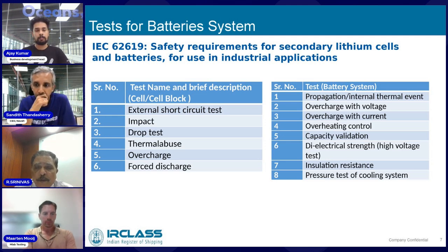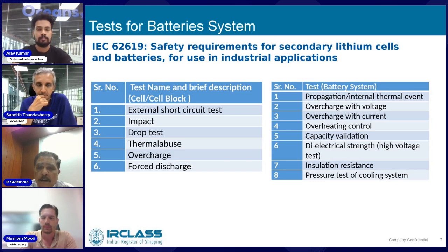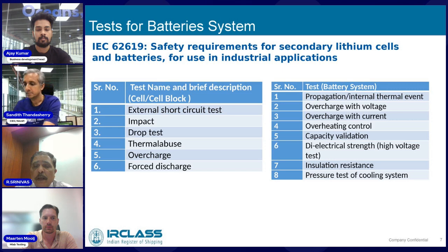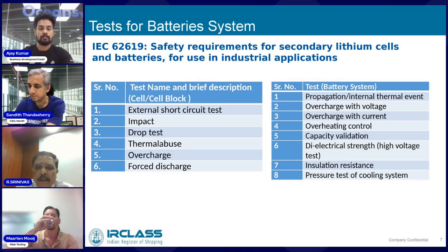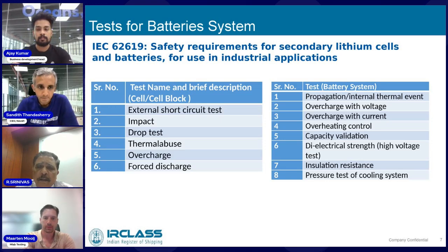There could also be a situation where we want to test module to module - if one module is on fire or has a thermal runaway, it shouldn't propagate to the other module. This test isn't compulsory, it could be case specific, but there are guidelines coming out at a later stage. Other tests include overcharge with voltage, overcharging with current, heating, and capacity validation.